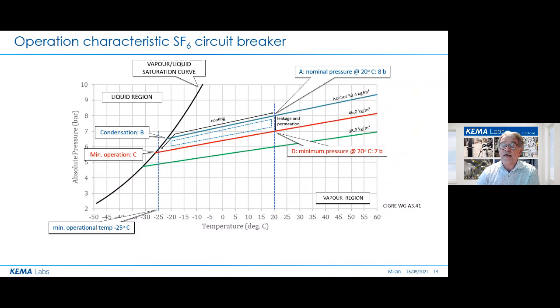Alternatively, a lower gas density can be chosen as the nominal condition, like point D. The advantage is a lower gas pressure, but now there is just enough gas inside, so no condensation is permitted at minimum temperature. Well, this is then the green track you see here. Whether to choose the blue or green track is a design choice.